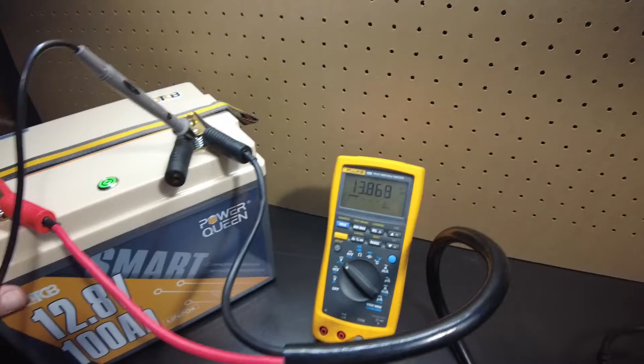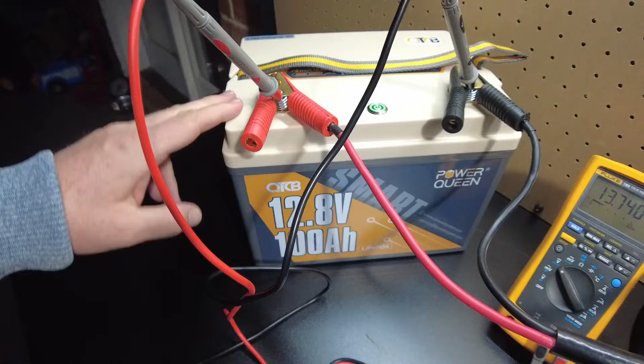That is fantastic, that's a good place for it to shut off at. That means it meets the specifications in the manual, and the cells should be quite balanced and well matched. Otherwise, if these batteries shut off a lot lower than what's specified, that would indicate there might be an imbalance in the cells, or that the cells weren't very well matched when they built the battery at the factory.